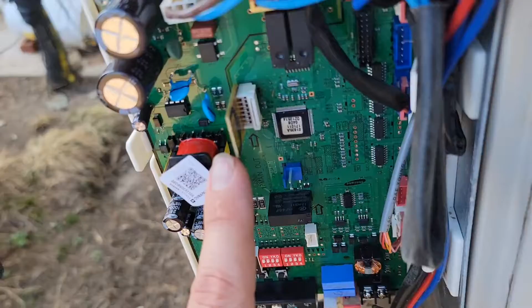To program the EEPROM for the outdoor unit, you need an SRC file. It's not like the indoor unit programming where all I have to do is go to VRF Coder, look up the model number for my indoor unit, and get a bunch of option codes I can use to write the option for the indoor unit. The outdoor unit needs that SRC file, so what I do is call Samsung Tech Support.